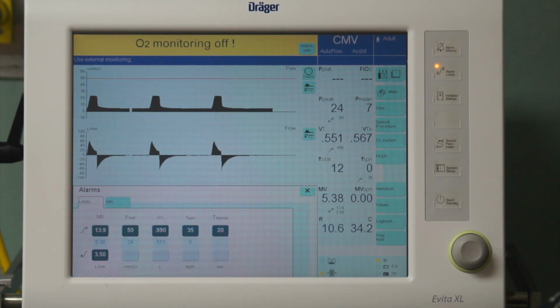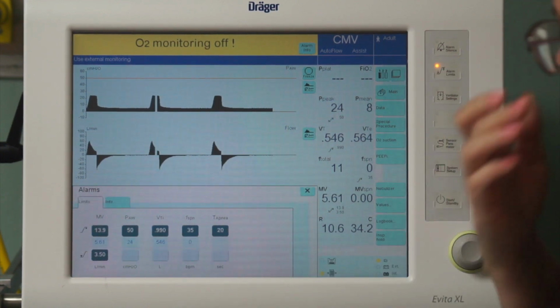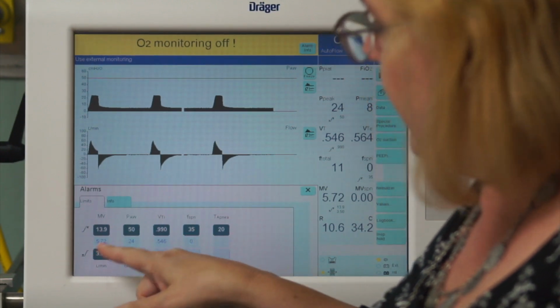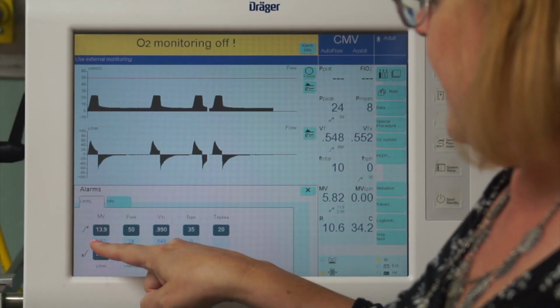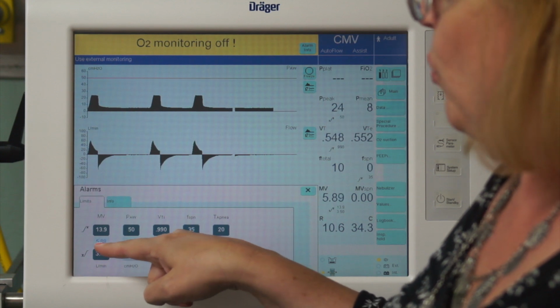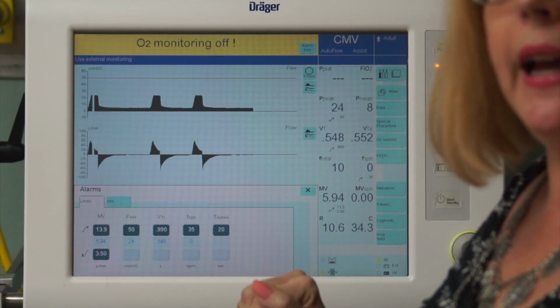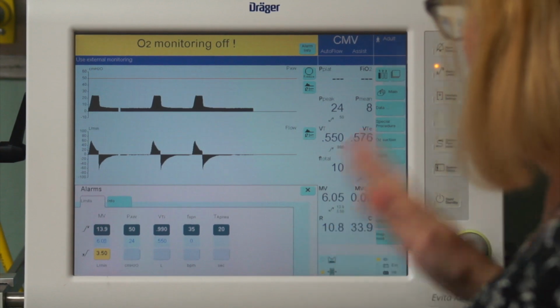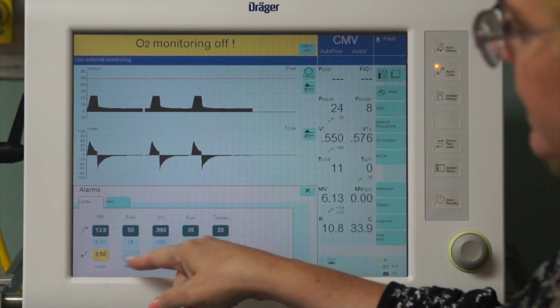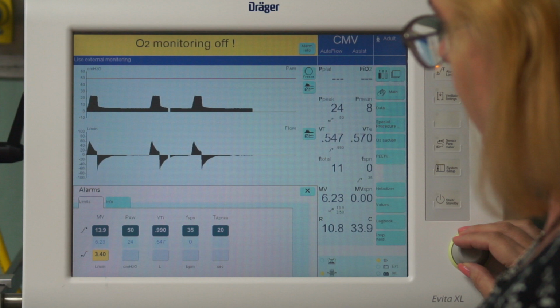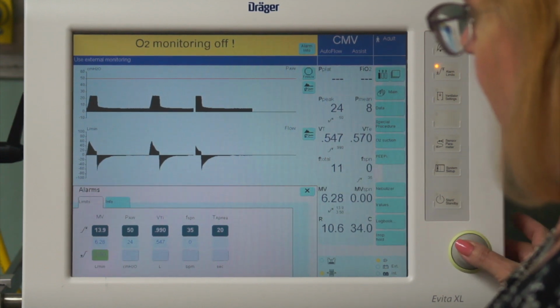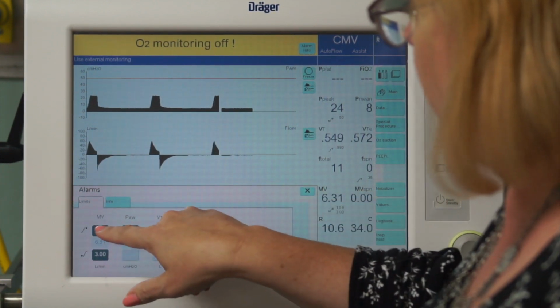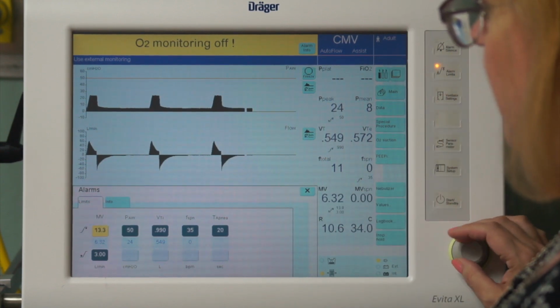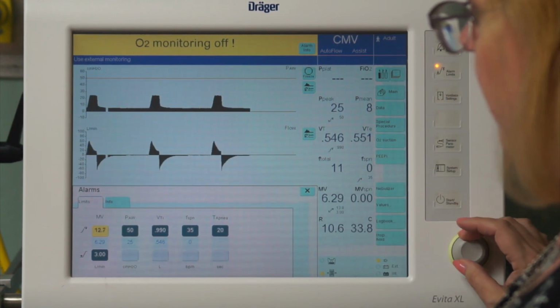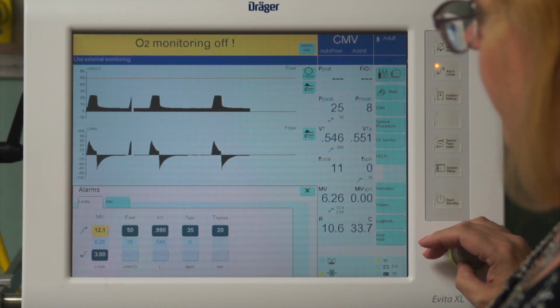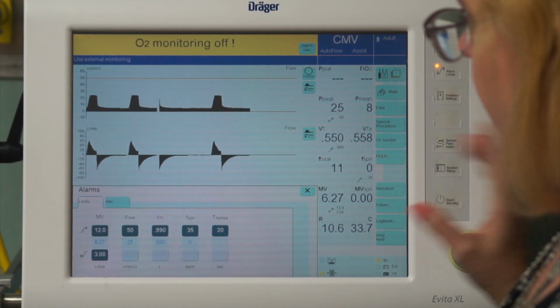So right up here, I'm going to press the alarm limit button, and I'm going to take a look at my alarms. And the nice thing about the Draeger is it tells me my actual minute volume right in the middle of my low and high alarm. So I don't even have to take the time to look over here. It's putting everything right in there. So I'm going to go ahead and take my low minute volume down, maybe take my high minute volume down just a smidge, even it out, not have a weird number there. Kind of got to go slow.